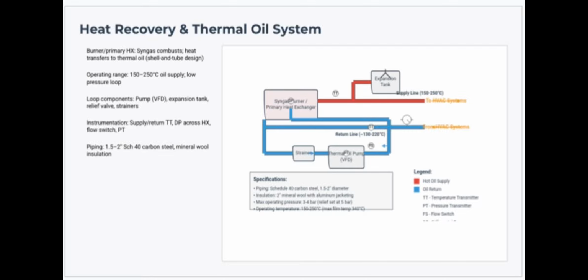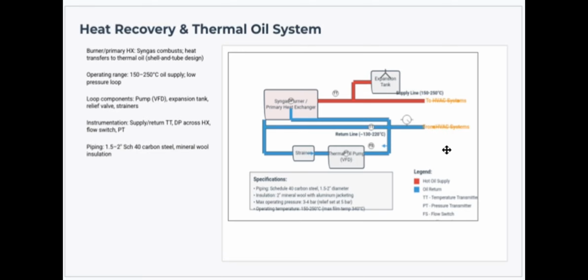The heat recovery and thermal oil system: burner/primary HX, syngas combusts, heat transfers to the thermal oil shell-and-tube design. Like I said, operation range is around 150 to 250 Celsius oil supply and a low pressure loop. Loop components: pump, VFD, expansion tank, relief valve, strainers. Instrumentation: we will do supply return TT, DP across HX, flow switch, PT. Piping: we will use around inch and a half to 2 inch schedule 40 carbon steel and mineral wool insulation. Basically, this is a little breakdown of what I got, a little diagram.